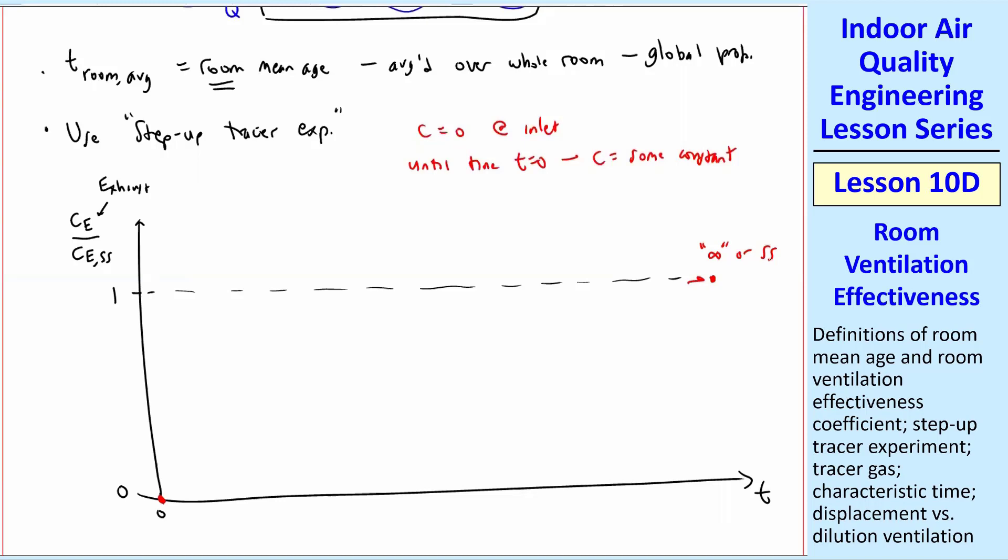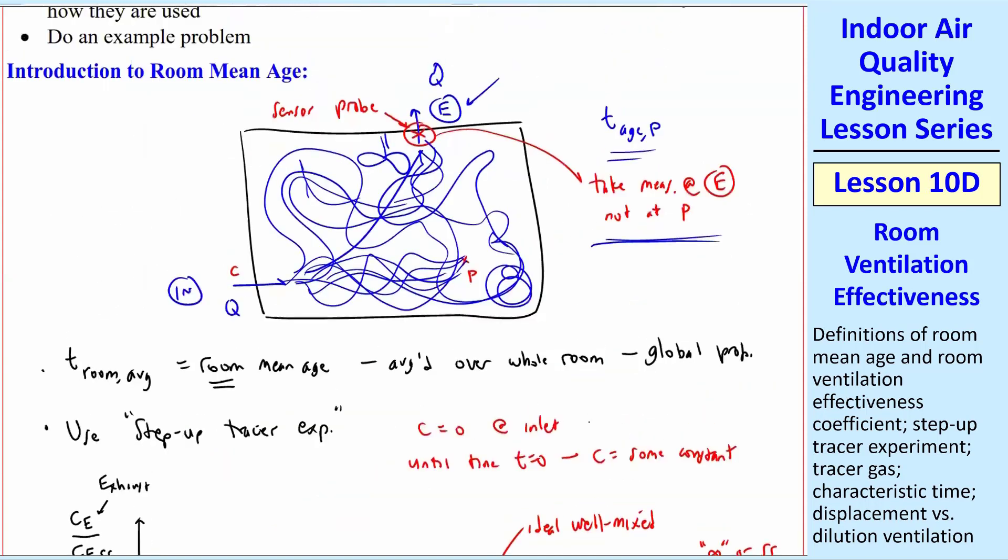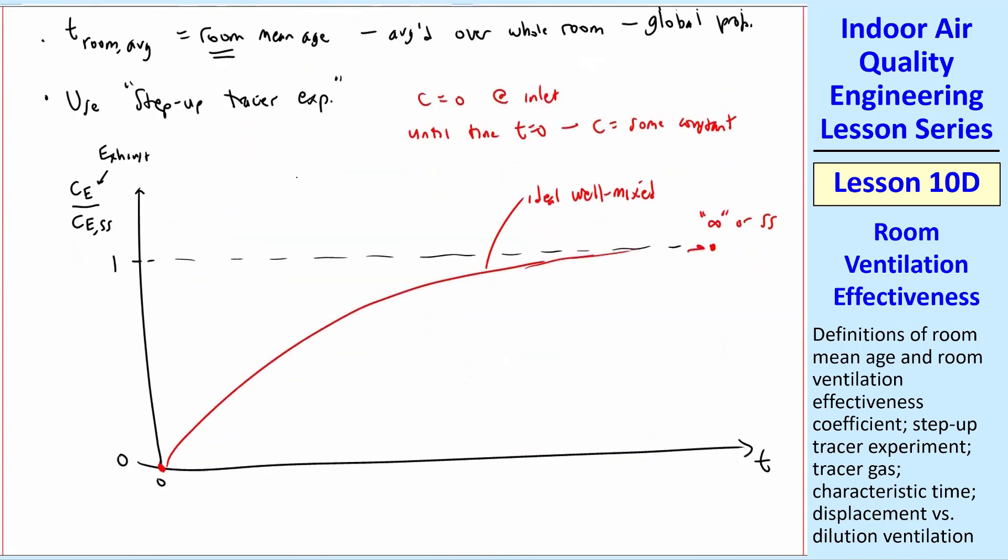We're going to get to C E equals C E steady state eventually. It may take longer for some rooms than others. If you do this with a perfectly well-mixed room, you would get our standard first-order ODE solution, but in real life, you may get something quite different. In a real room, you start injecting this contaminant at time T equals zero, and you're not going to sense it for a while. It's not perfectly well-mixed. It'll take some time, so normally the curve doesn't look like that, but it starts out at zero, and then it'll start slowly increasing, and it might have some wiggles in it and stuff, but eventually it's going to get to C E.